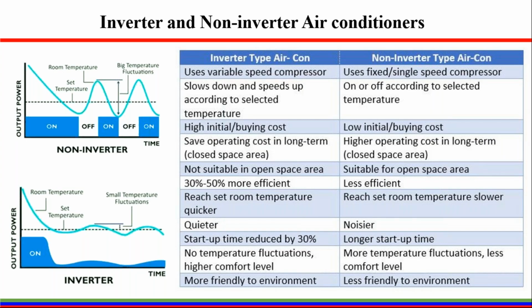This is the diagram which shows how the compressor works. On the left side of the slide, you can see this diagram. The upper diagram is for the non-inverter air conditioners, and the lower diagram is for the inverter air conditioners. And you can see how the compressor is working in the inverter air conditioner and in the non-inverter air conditioners. In the inverter air conditioners, the starting power of the compressor is higher as compared to the non-inverter air conditioner, but the rest you can see.